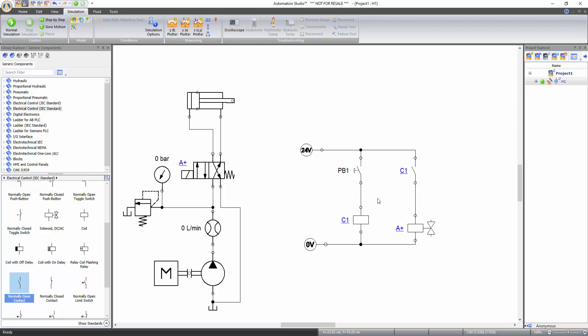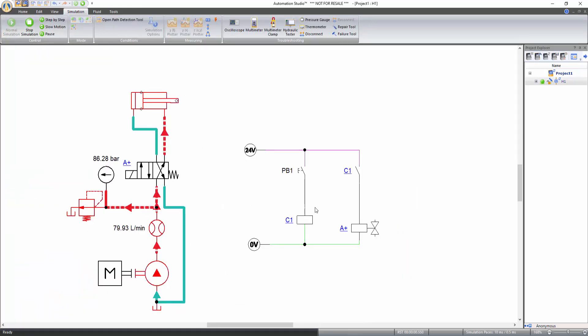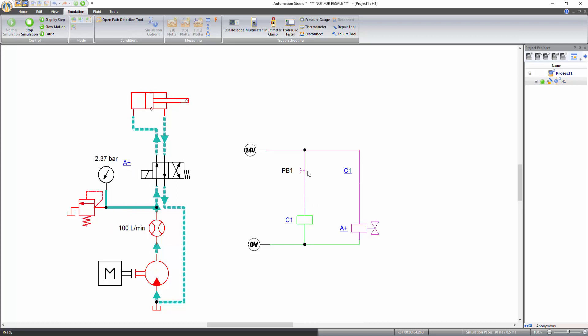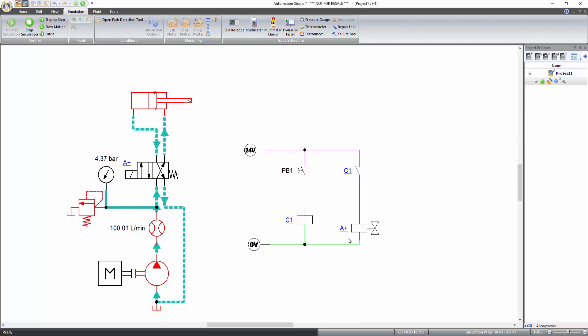Now that the links are made and the aliases are the same between the hydraulic and electrical control circuit, the circuit is ready to be simulated using both technologies. Start the simulation. Click on PB1 and latch it in order to activate the push button and energize the solenoid A+. Observe that the directional valve changes its position and allows flow through the piston end of the cylinder, which results in its extension. When you click on the push button again, the solenoid is de-energized and the directional valve moves back to its initial position, allowing flow through the rod end of the cylinder, which results in its retraction. In this way you can create different hydraulic and electro-hydraulic circuits.